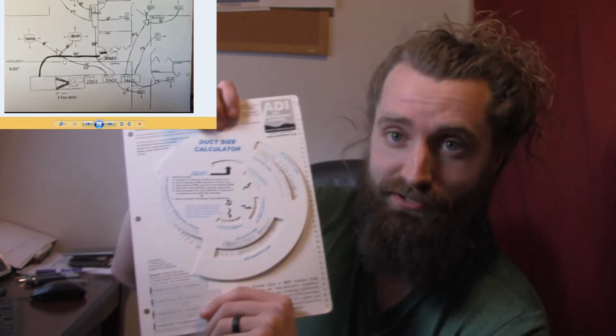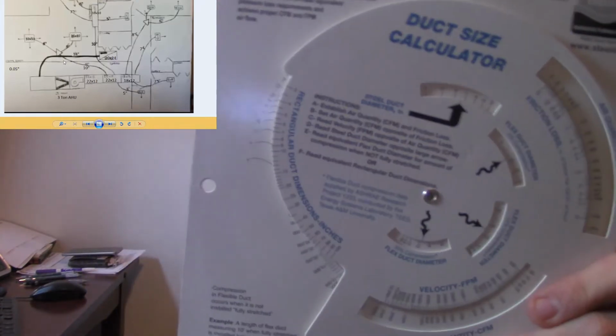Nine times out of 10, it is very probable that your installers are not actually installing flex duct the way it's supposed to be. They're not. You don't have two guys stretching that flex duct out for 60 seconds and then installing it in nice, short, straight lengths. The likelihood that that is happening is very slim. So this duct calculator takes into account compression. We've got 3 different categories here: a 4% compression, a 15% compression, and then a 30% compression on the bottom.